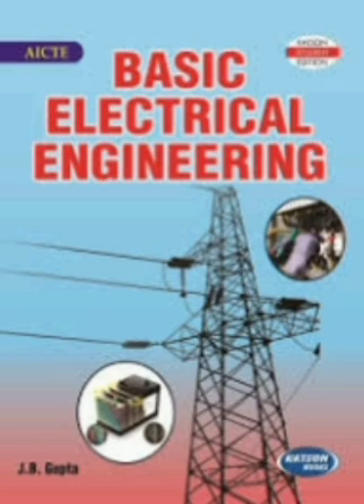Core type transformer, shell type transformer. First one, core type transformer: series magnetic circuit, 2 limb and 2 yoke. Core type transformer is suitable for low flux density applications. Core type transformer requires more amount of copper. Core type transformer requires less amount of insulation, so it is suitable for high voltages and high power applications.